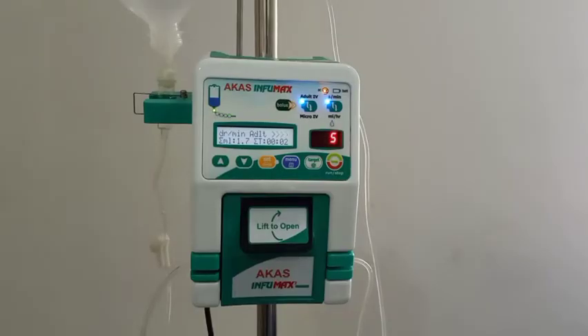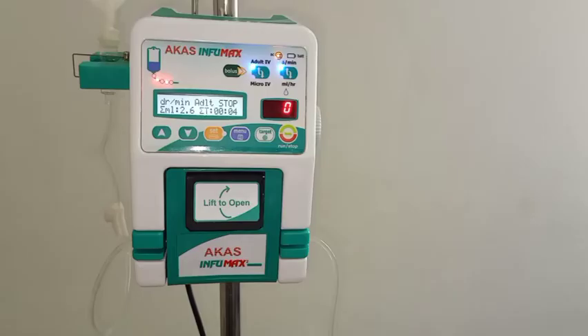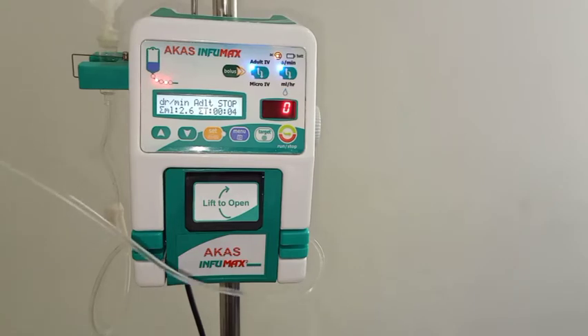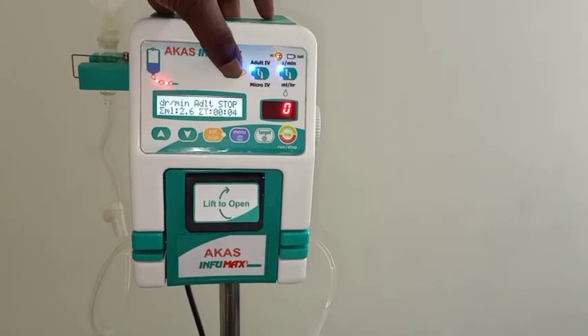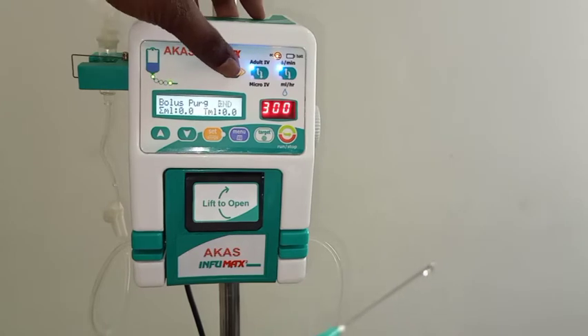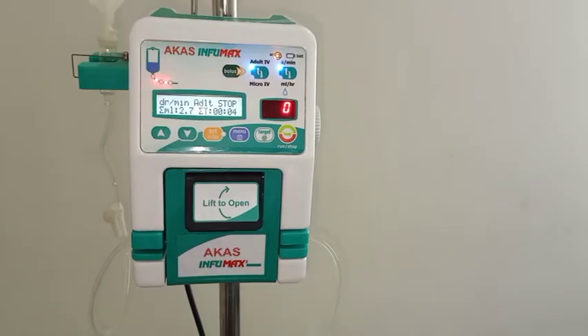Hi everyone, here we are going to see the IVTube calibration of Infomax. Before entering into the calibration, ensure that there is no air bubble inside the IVTube. So first we have to do priming by long pressing the bolus key. Now I have removed all the air bubbles inside the IVTube and we are going for IVTube calibration.